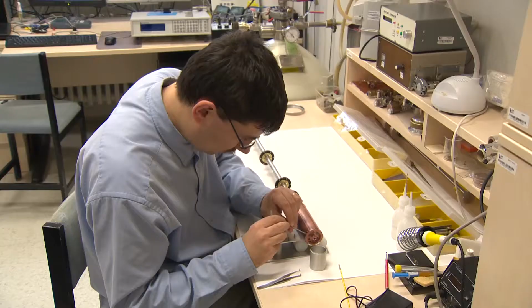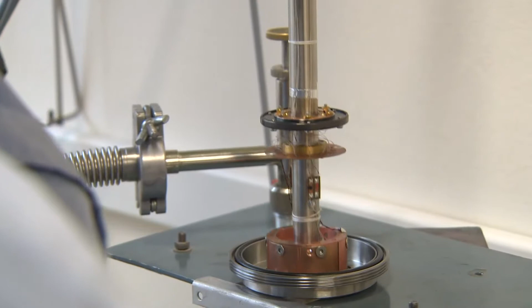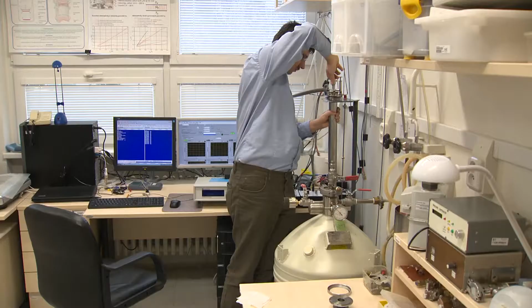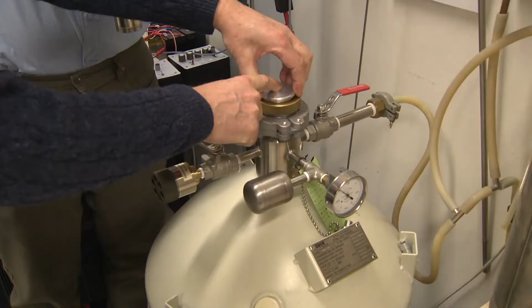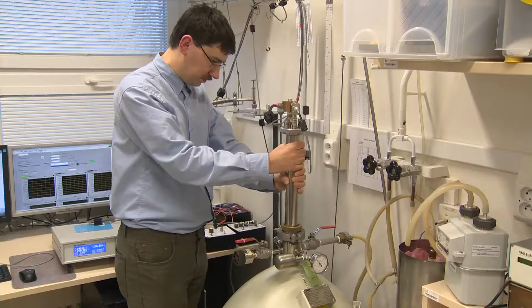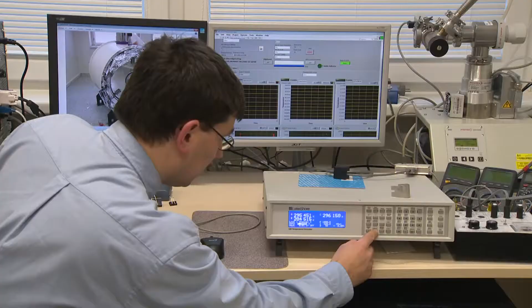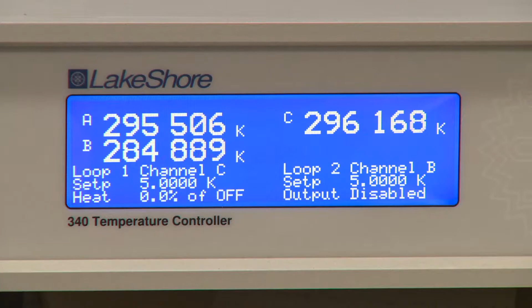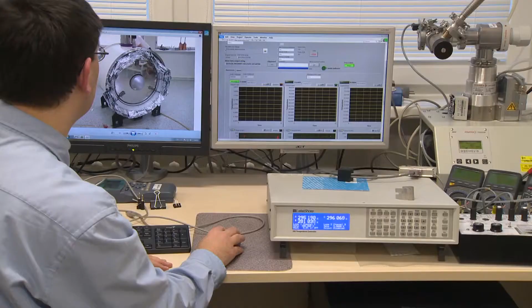By measuring heat flow in a vacuum between two separate surfaces, we can determine how these surfaces reflect or absorb thermal radiation in a defined temperature range. The special measuring device developed at the Institute of Scientific Instruments can accurately measure such a heat flow from minus 260 degrees Celsius, and it also manages to measure the heat flow with a very large range of measured output.